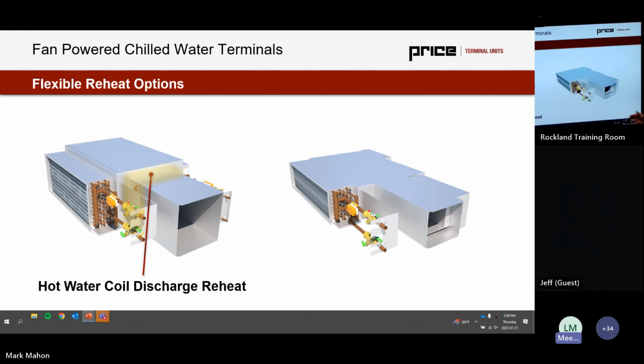Now, in the wake of further decarbonization and electrification, the utilization of air source heat pumps, we're seeing 120, we're seeing 110. I saw a project with water source heat pumps in Seattle that had 96 degree entering water. We can't do that with the typical coil anymore, so we need another alternative option. Maybe we do a 4-row coil. That's not ideal for pressure, watts per CFM. So maybe instead we'd use electric coil discharge reheat. Very low pressure drop, very high capacity, very immediate response to a call for heat. Not loved by every market, so a good solution, but dependent on the locality, whether or not it can and will be used.